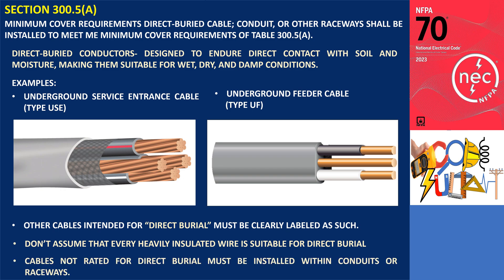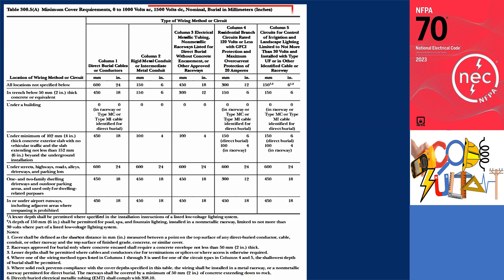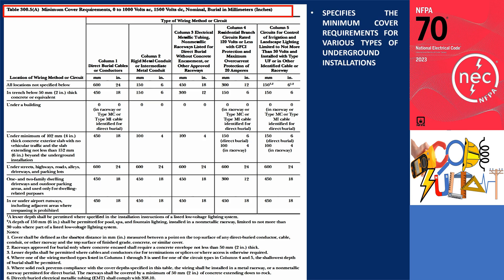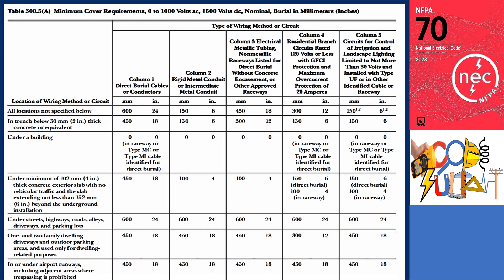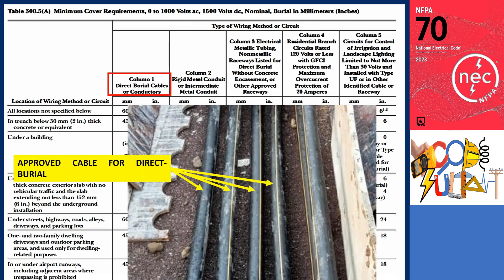Cables not rated for direct burial must be installed within conduits or raceways. Table 300.5(a) of the National Electrical Code specifies the minimum cover requirements for various types of underground installations for 0 to 1000 volts AC, 1,500 volts DC nominal, with burial measurements in millimeters and inches. It details the depths at which different electrical conductors and raceways must be buried to ensure safety and compliance. Table 300.5(a) contains five different types of wiring methods or circuits. Column 1 is for direct burial cables or conductors — cables not installed in conduits or any raceways.